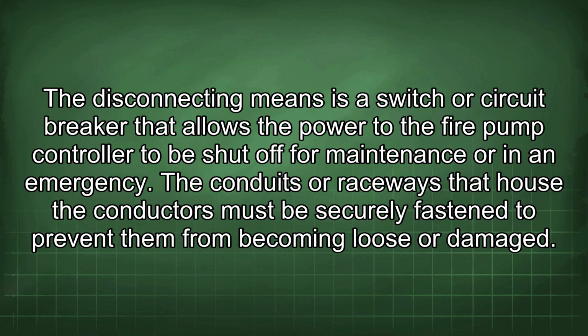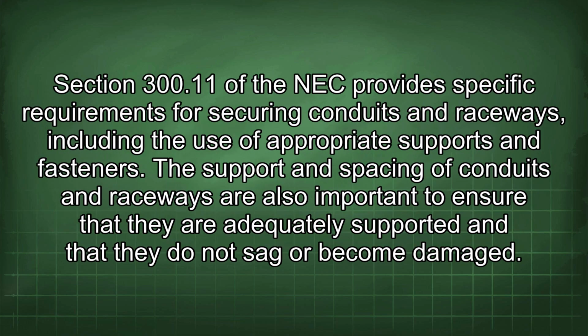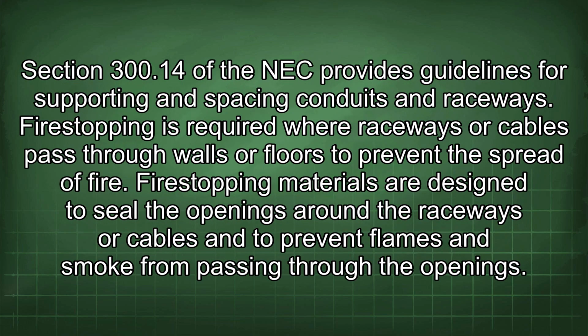The conduits or raceways that house the conductors must be securely fastened to prevent them from becoming loose or damaged. Section 300.11 of the NEC provides specific requirements for securing conduits and raceways, including the use of appropriate supports and fasteners. The support and spacing of conduits and raceways are also important to ensure that they are adequately supported and that they do not sag or become damaged. Section 300.14 of the NEC provides guidelines for supporting and spacing conduits and raceways.